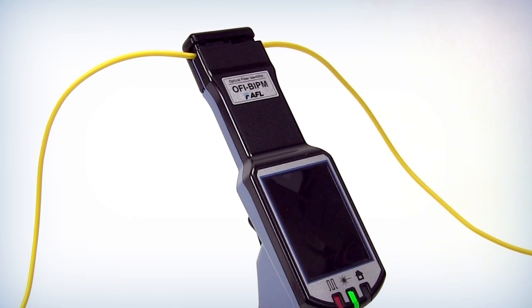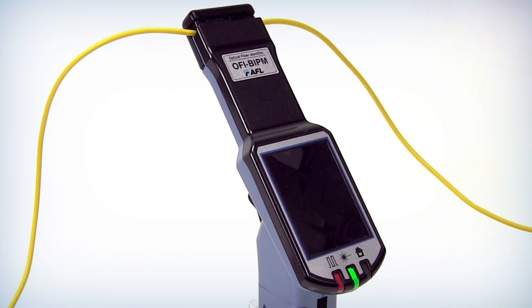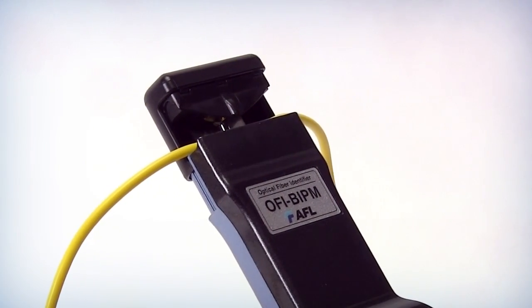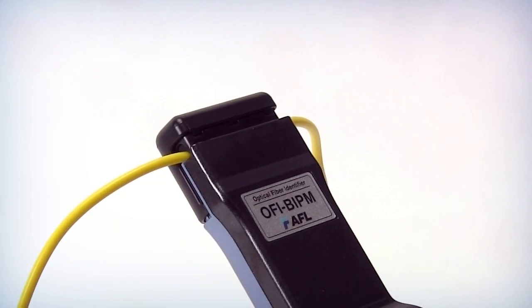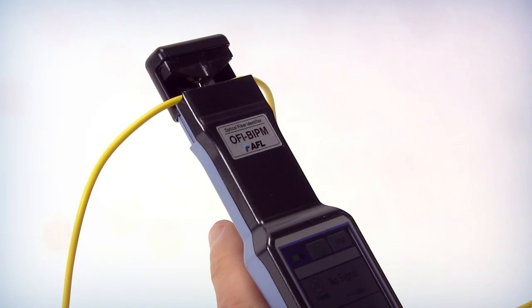Testing should be performed on a fiber at a distance of 6 to 18 inches from the connection point. Limit the time the fiber is under test. Clamp the OFI-BIPM on, read the results, and then quickly release and remove the OFI-BIPM.